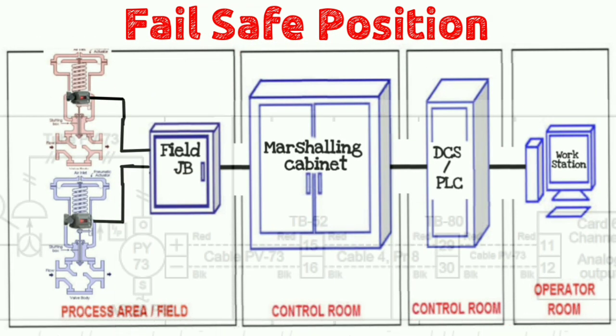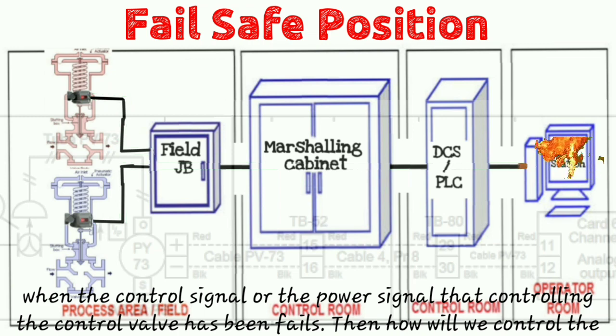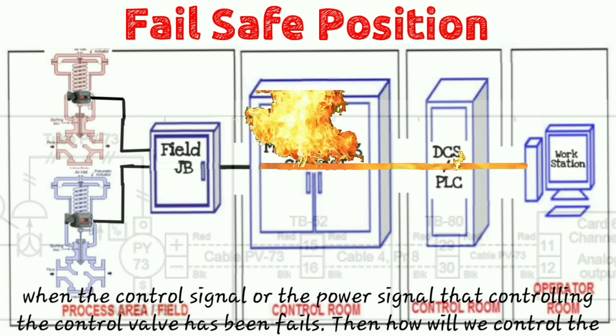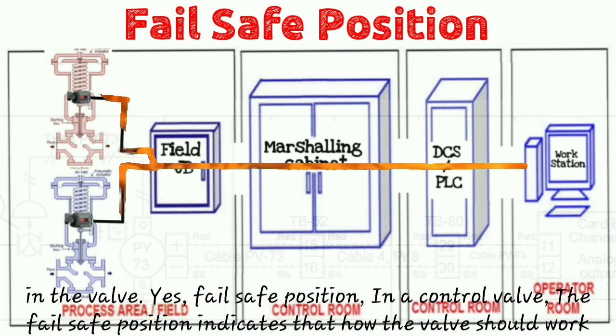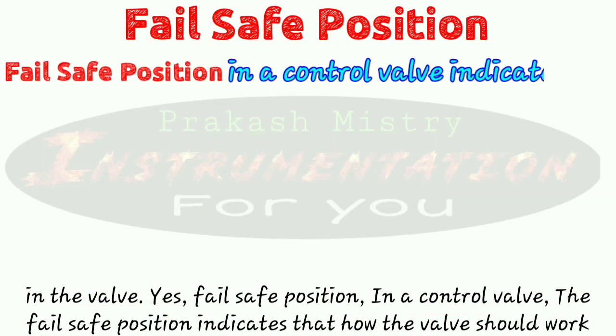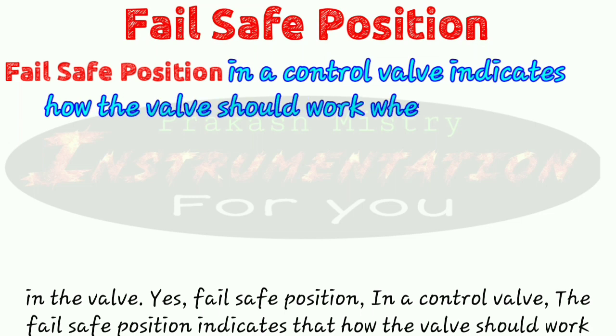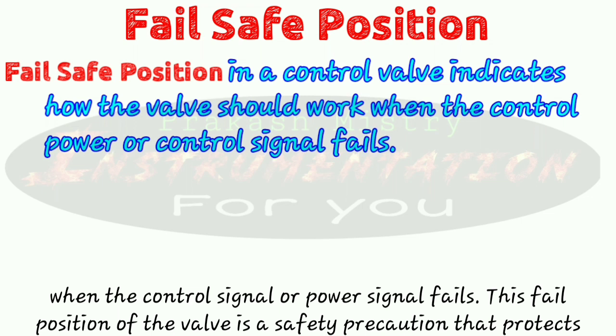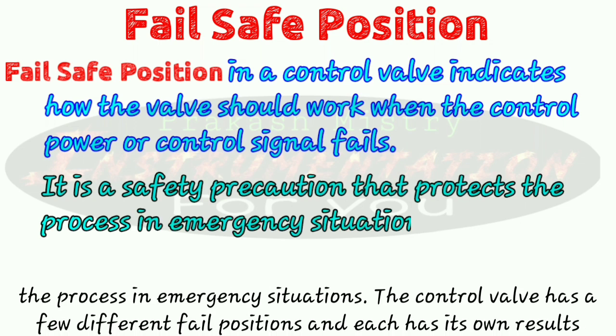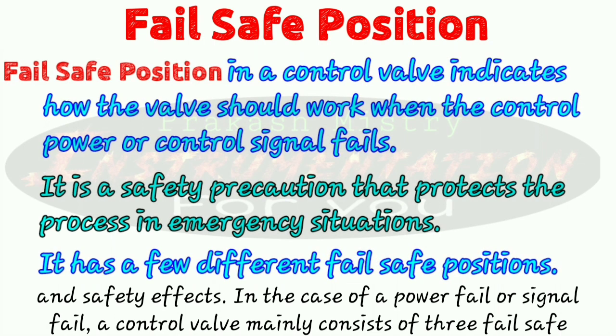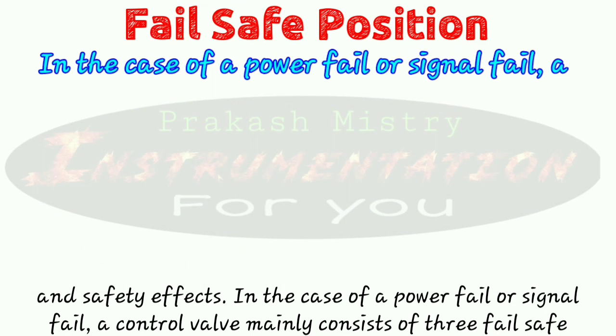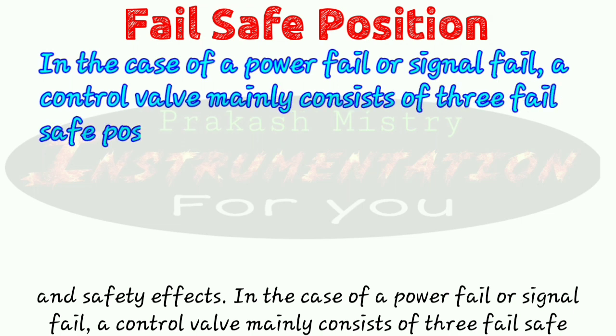But imagine what will happen when the control signal or power signal controlling the control valve fails. How will we control the process? How will we keep the plant in safe condition? That's why it is so important to choose the correct fail-safe position in the control valve. The fail-safe position indicates how the valve should work when the control signal or power signal fails. This fail-safe position is a safety precaution that protects the process in an emergency situation. In the case of power fail or signal fail, a control valve mainly consists of three fail-safe positions.